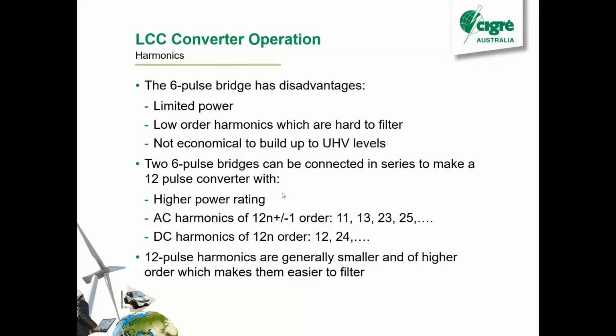So what you can do is connect 2 6-pulse bridges in series and make a 12-pulse converter. So the good thing with a 12-pulse converter is you can have your higher power rating. You've got your 2 6-pulse bridges, and your harmonics go up to 12n plus or minus 1. So our worst harmonic then becomes the 11th. We've got 13th, 23rd, 25th, and the DC harmonics are 12n, so 12th, 24th.